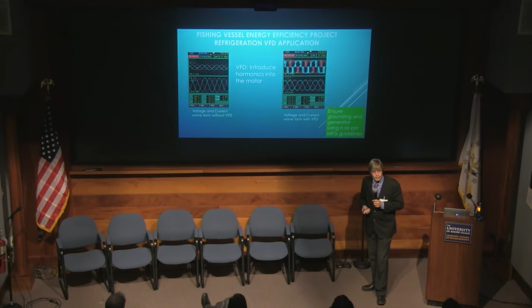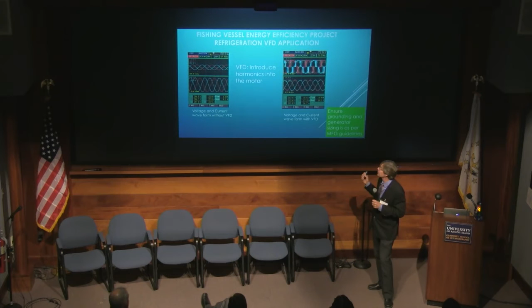As with everything with new technology, we need to be careful about how we install it. VFDs are great for these variable loads, but the issues that I've heard over the past with them not working right are typically from lack of following the manufacturer's instructions. Anytime you change power from one form to another for AC current, you have harmonics. You can see here's a nice clean sine wave, here isn't. So if you're looking at doing this, just make sure you follow the manufacturer's instructions. Grounding is actually essential to be done the way they say to do it.